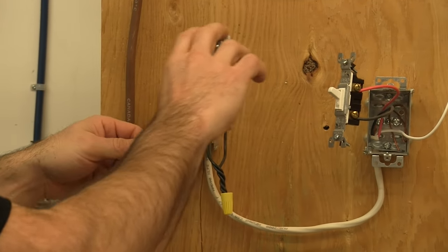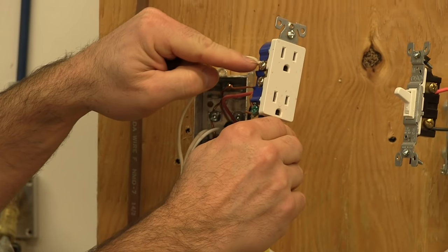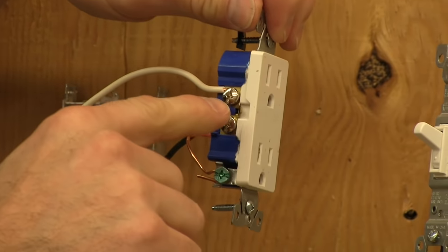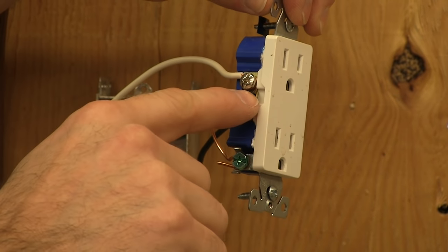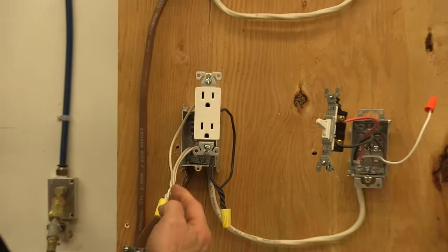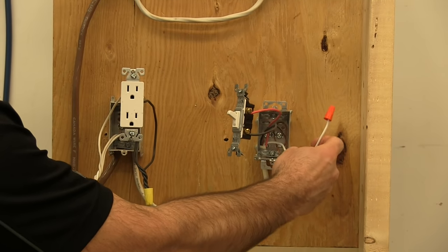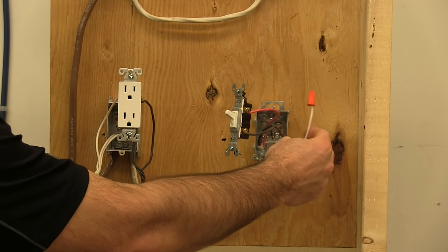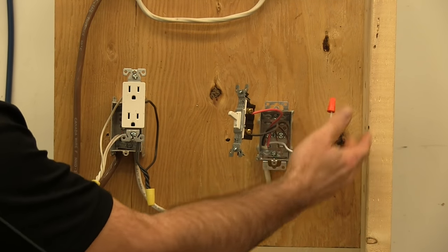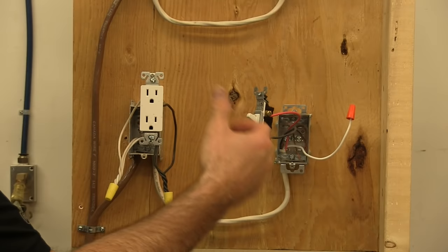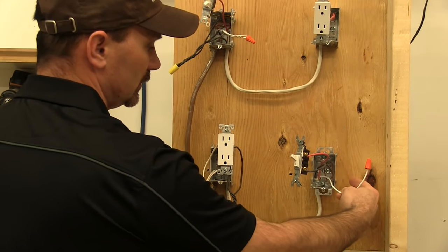As far as the neutrals go, neutrals are all just pigtailed together. Got a jumper coming off going to the neutral side. We don't break the tab out here, okay? Because both of these can still share the same neutral, so this tab does not get broke out. The other neutral line is heading over to the switch. In a lot of areas now, they're asking by code to have a neutral available at every switch location. So in this case we're not using it—I've just capped it off. We don't need it. If you had a dimmer or a timer, some of them would require that you need that, and that's why they're asking in the new codes to put it there.